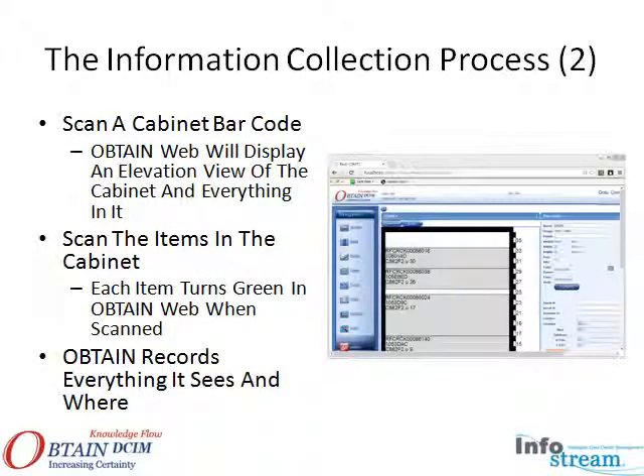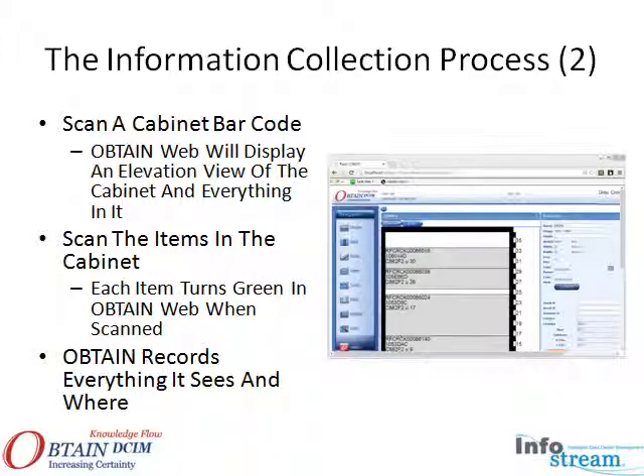When a cabinet label is scanned, the Obtain mobile device will display an elevation view of the cabinet with all the devices Obtain knows about. As each device is scanned, it will turn green in the Obtain web display. Once the user scans all the devices in a cabinet, they simply move to the next cabinet and scan the cabinet label. Obtain displays that cabinet and the user again scans all the devices. The collection process proceeds in a fraction of the time it would take to manually collect text information.